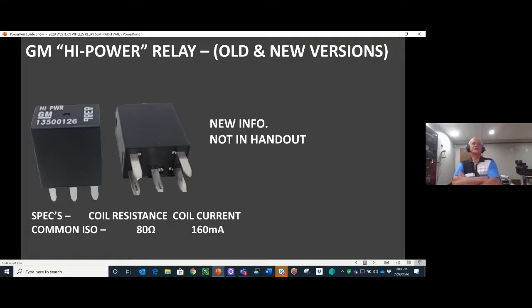So now we have two types of GM high power relays, and it's important for you to know the difference, and I'll explain why shortly. This is not in your existing handout, nor are bistables, but it will be in the new handout. Notice that the common one is on the left. It says high power on it. There's the part number for it from GM. The resistance spec for the coil is 80 ohms. That's right in the middle of the ballpark for all ISO relays, isn't it? And the coil current is about 160 milliamps. That's normal.